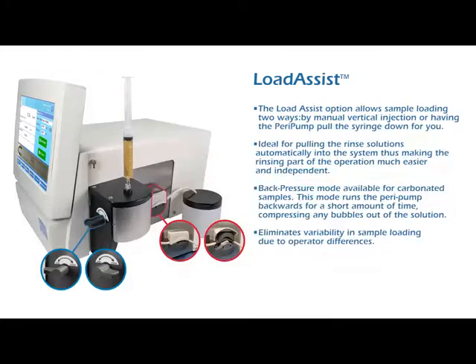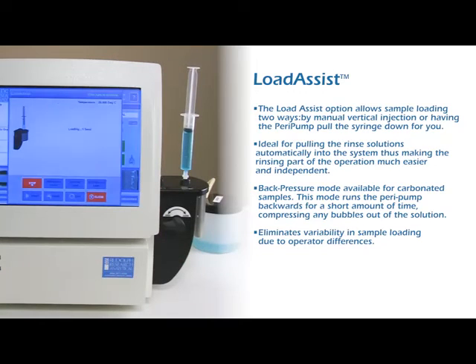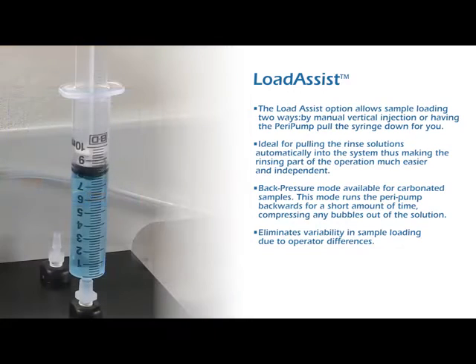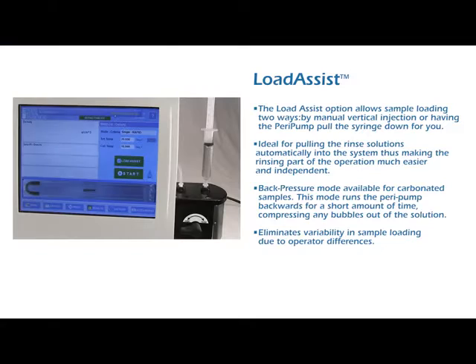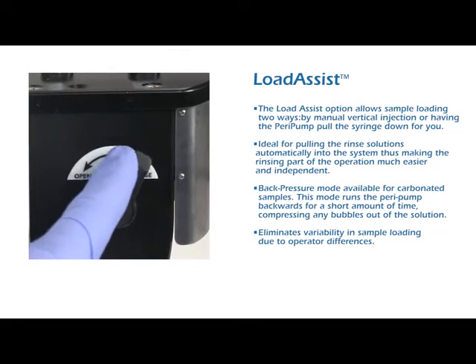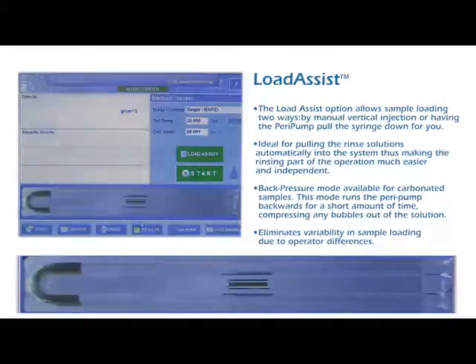Load assist: the load assist option allows sample loading two ways — by manual vertical injection or having the PeriPump pull the syringe down for you. Ideal for pulling rinse solutions automatically into the system, making the rinsing part of the operation much easier and independent. Back pressure mode is available for carbonated samples; this mode runs the PeriPump backwards for a short period of time, compressing any bubbles out of the solution. Eliminates variability in sample loading due to operator differences.